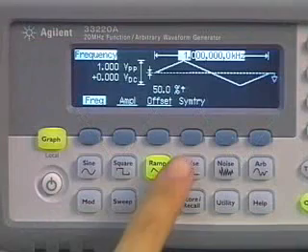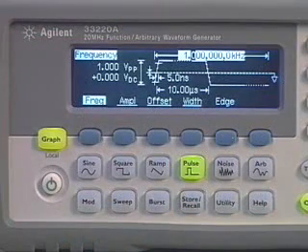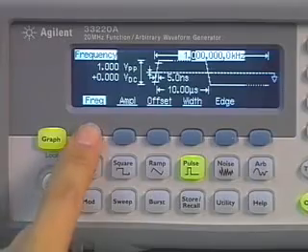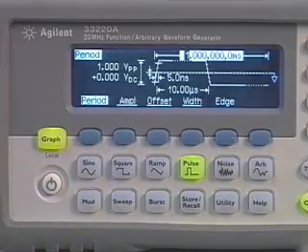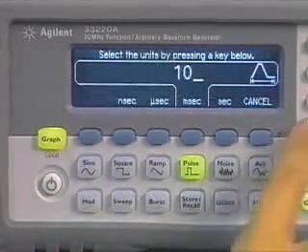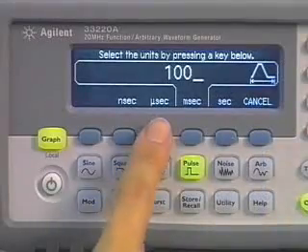The 33220A can be used as a low cost pulse generator. The cycle time can be set as either frequency or period. I prefer period. Let's create a 10 microsecond pulse with a 100 microsecond period.